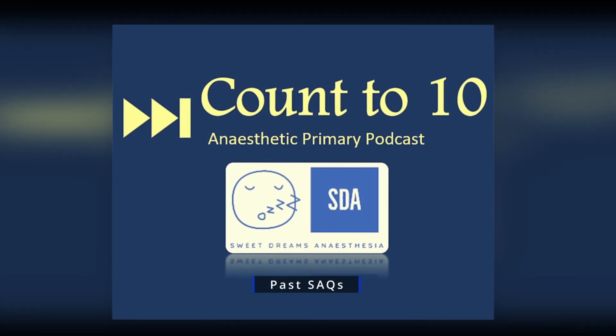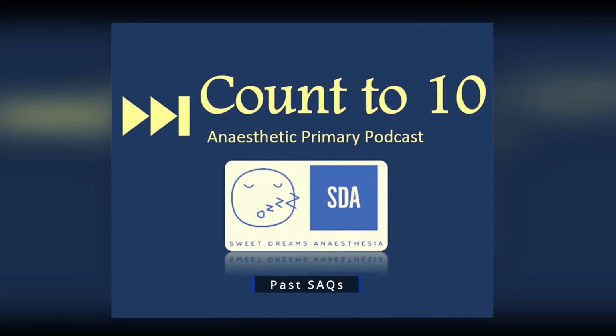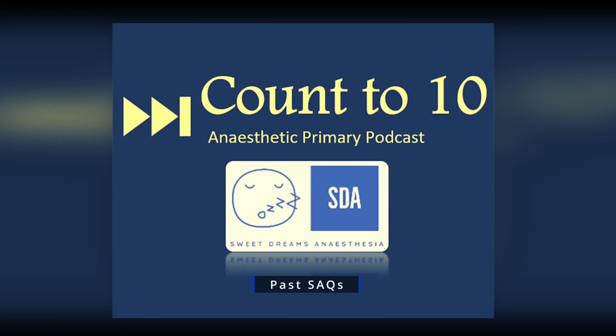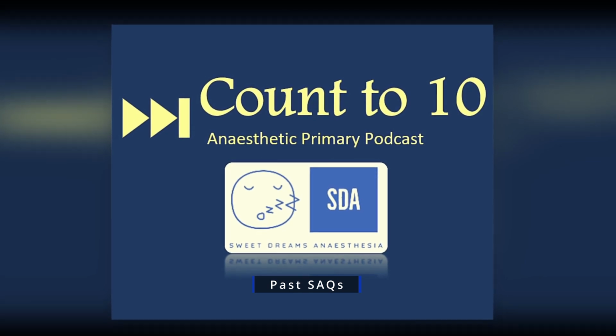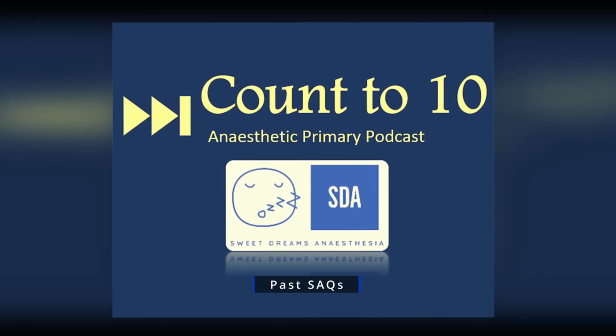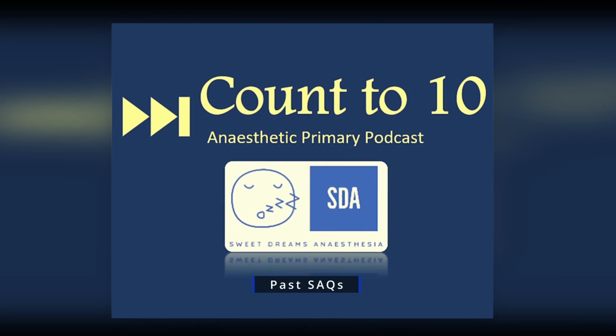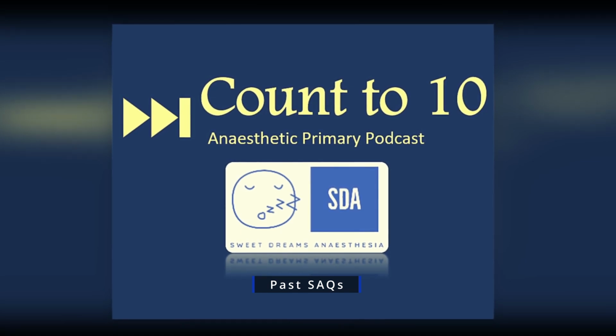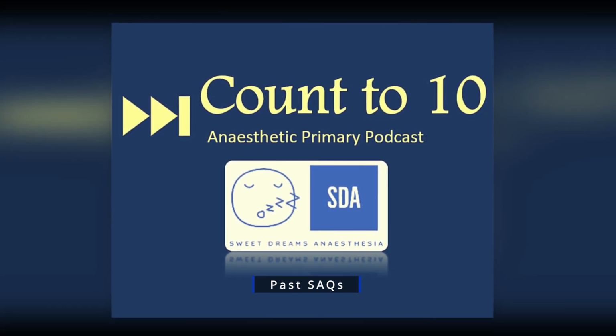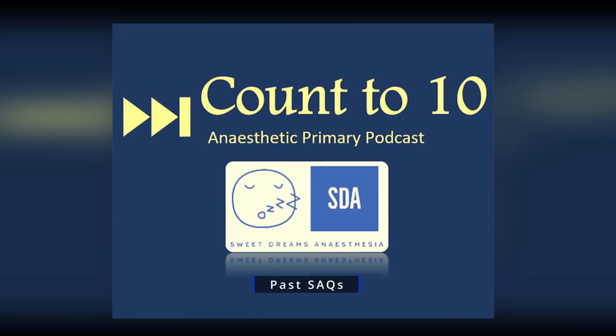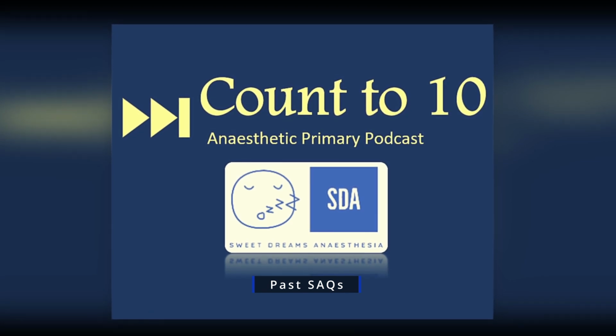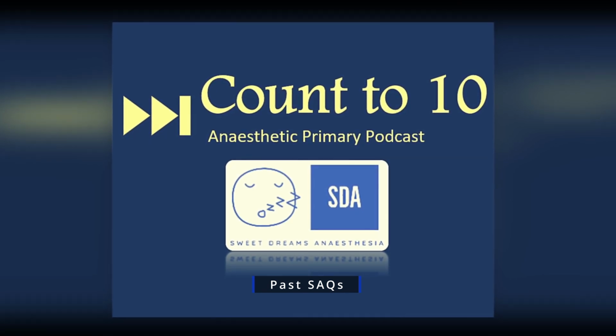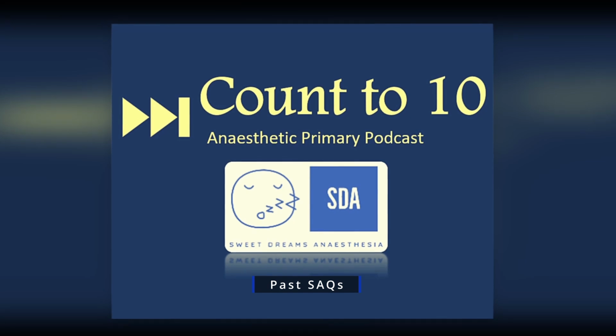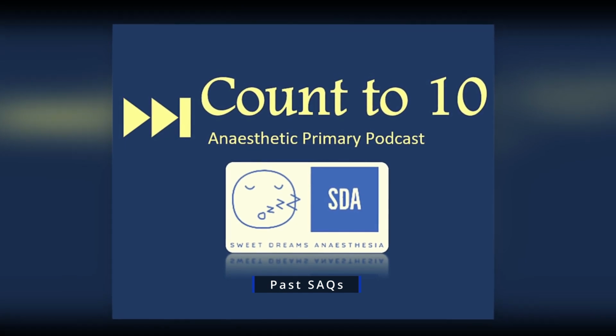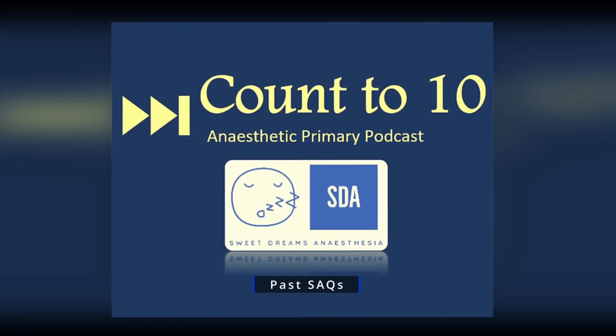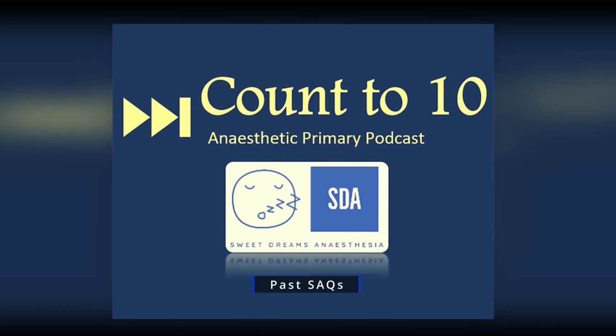Then moving on to the second part of this question, which is the sources of error, again dividing this into static and dynamic, and we've covered these ad nauseam. Static errors are zeroing and leveling, and the key thing I would state with static errors is they can affect systolic, diastolic, and mean arterial pressure. In comparison, dynamic errors affect only systolic and diastolic pressure, but the mean arterial pressure should remain accurate.